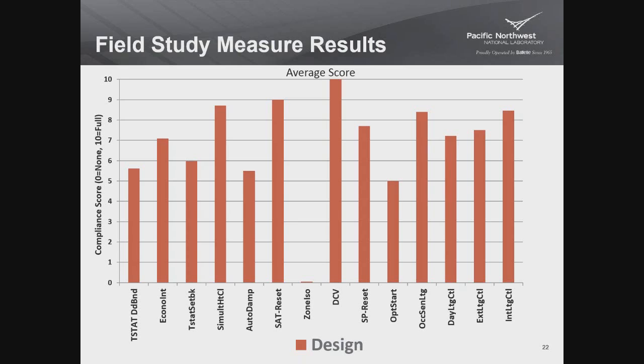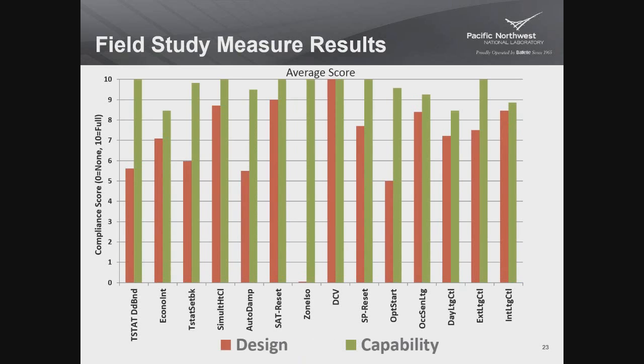Zone isolation, this one's a little misleading. It says it was never included in the design. But this one, there was only one observation. Only one of the 24 buildings required zone isolation, and it wasn't in there. So there's not much of a takeaway, I think, from this with an N equal 1 here. The others have a little bit of a range. It ranged from about 50% or from score 5 up to 90, just sort of a range, so you can see that. So there's a lot more detail in the report, including a bunch of statistical analysis, and there's a link to the report at the end so you guys can dig in deeper there.